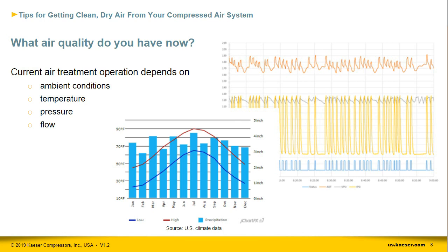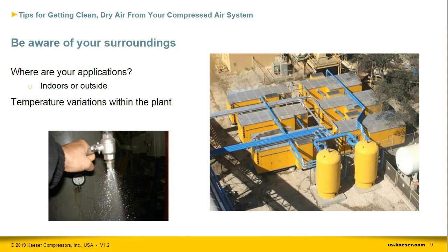Further, a couple of key points to look at: where is your equipment installed? Is it inside of a building or is it outside of a building? Is the area heated or is it cooled? Is there enough of that heating or cooling to ensure that your compressor is at correct operating temperatures?